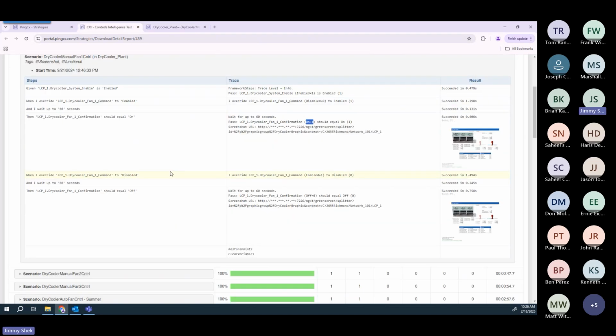So to continue on with this test scenario, we enable the fan, check confirmation, and then in this test, we're kind of doing the reverse, right? So here, we're overriding the fan1 command to be disabled, waiting up to 60 seconds, and then the expectation is that we would lose confirmation, right?